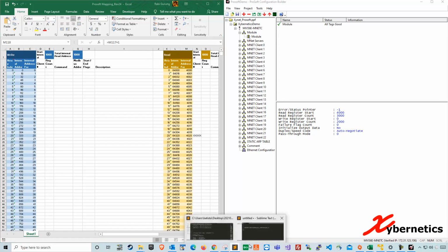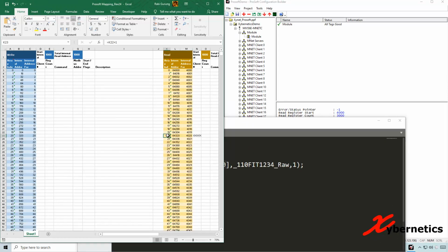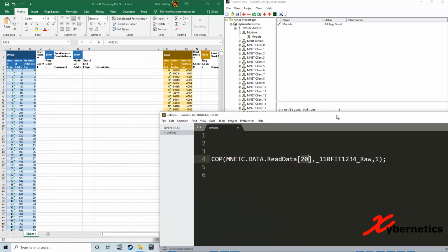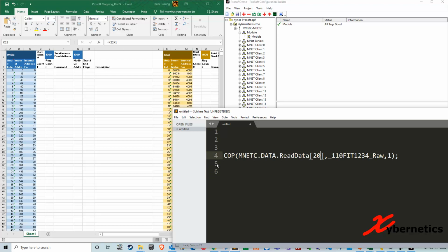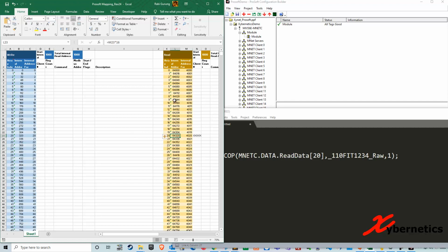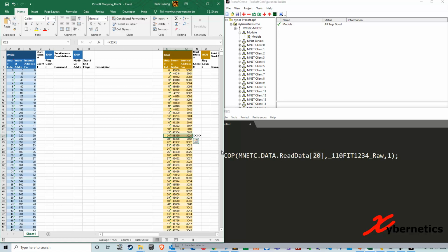So when the PLC program says read 20, again you're looking at this, but your index location is different. The bottom line is that you can change your internal register as much as you want, but your index will never change. That's the beauty of it. You don't have to revamp your program. Same goes for the internal address bit. You can change all you want. If I change this to 3000, the starting register, you can see all my internal address with the bit changes too. But you can specify that and you will still read that spot on the memory allocation.